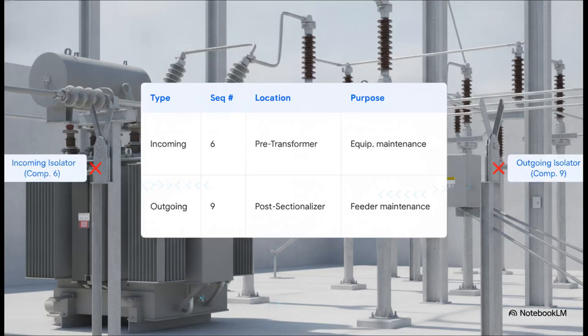Pretty smart, right? Now we already saw component 6, the incoming isolator right before the transformer. But notice here we have component 9, a second isolator or disconnector located just after the sectionalizer on the outgoing side. You might be wondering, why do we need 2? Well, just like the first one allowed for safe, visible maintenance of the main substation equipment, this outgoing isolator does the exact same thing on the back end, providing crucial visible isolation to ensure safe maintenance of the outgoing feeder lines or any specific outgoing equipment.